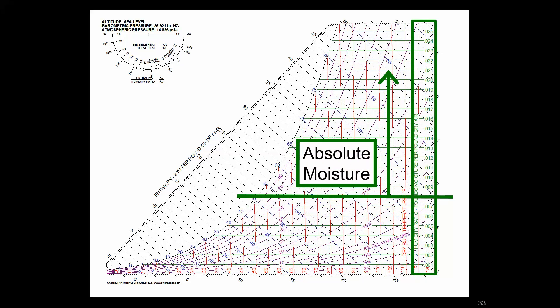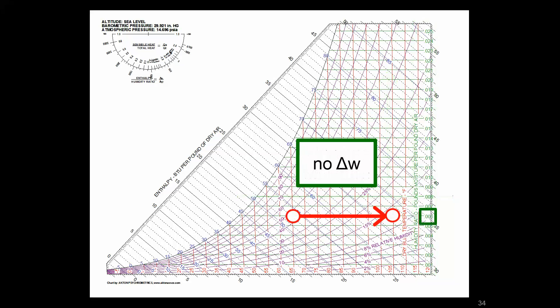Going to the y-axis, now we're introducing moisture and we call this absolute moisture. We're looking at how much moisture is actually entrained in the air, represented with the humidity ratio: pounds of moisture per pound of dry air, or grains of moisture. In our example, we're not changing how much moisture in the air just by straight heating, so there's a delta of 0 pounds of moisture per pound of dry air change.